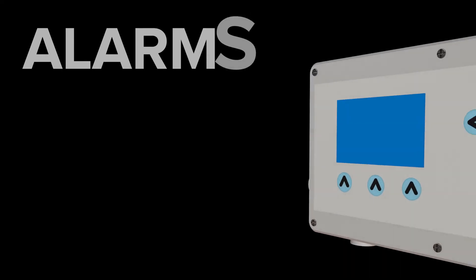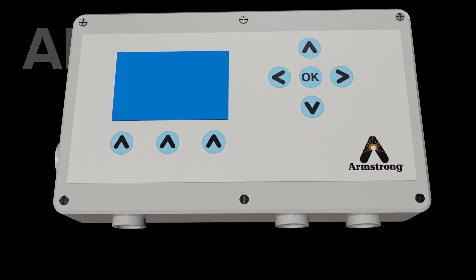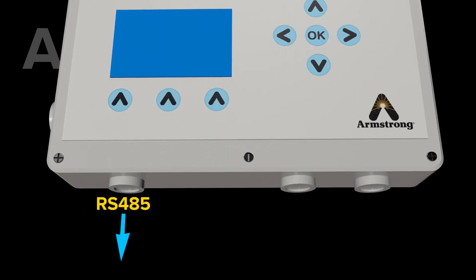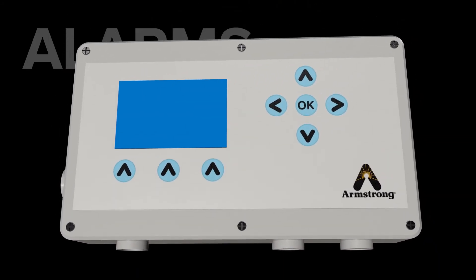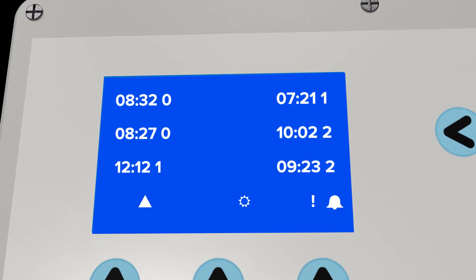The Steam QM1 monitors dryness fraction and alerts you with an alarm if there is a steam quality problem. It also offers a user-defined alarm through the RS-485 interface with Modbus protocol. An alarm does not affect measurements but does show up as a highlight on the screen. The user-defined alarm allows a user-defined limit for dryness when that limit exceeds 2 seconds.